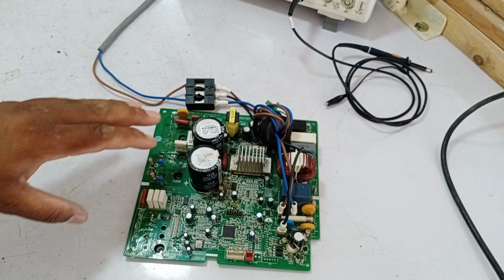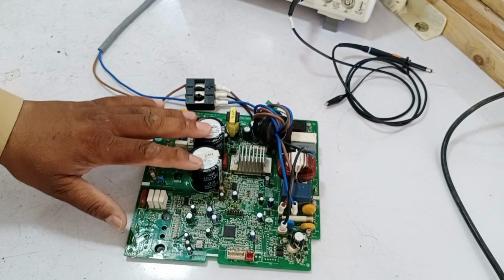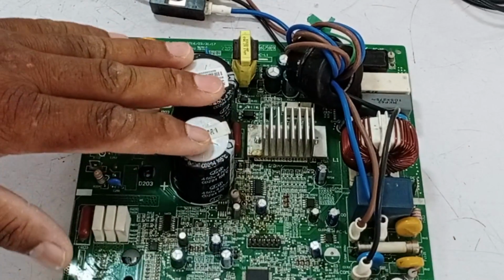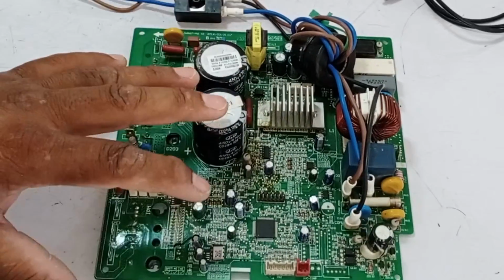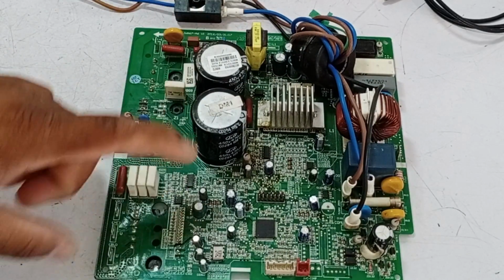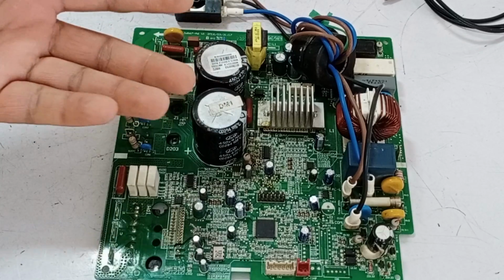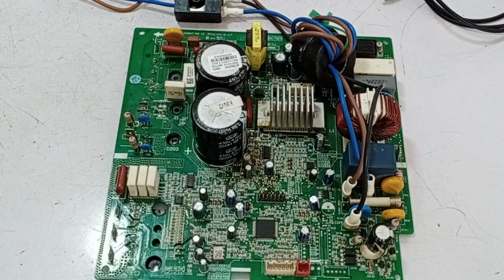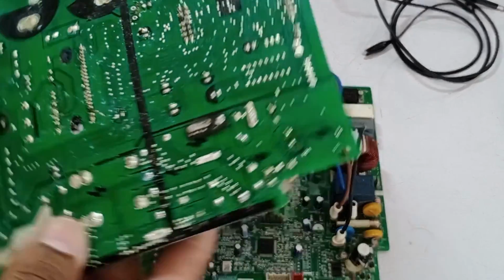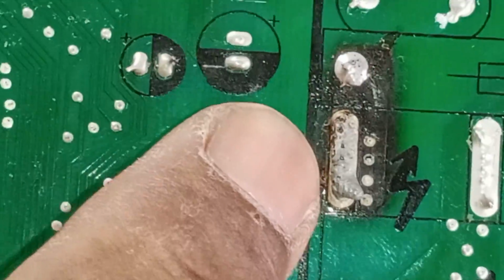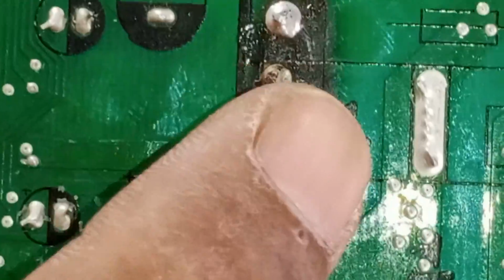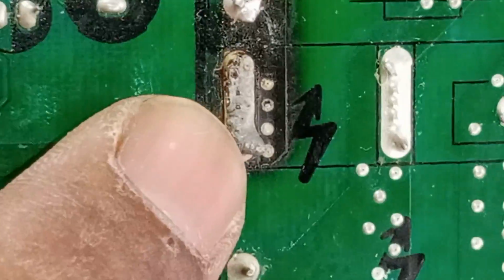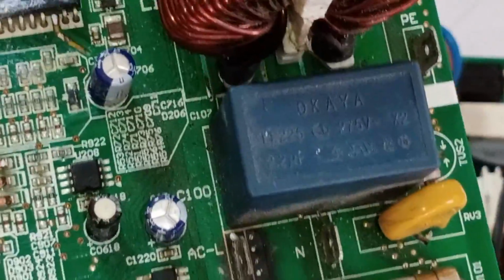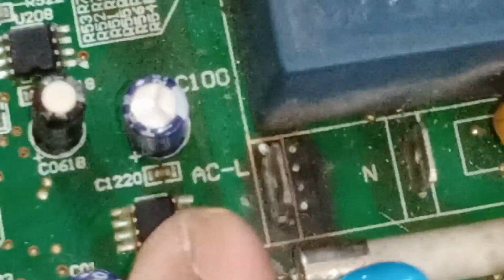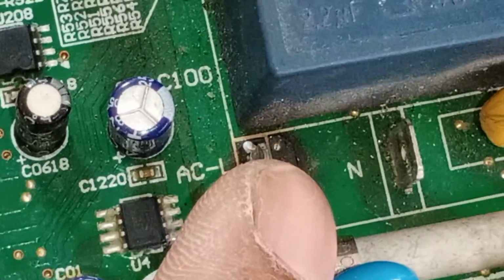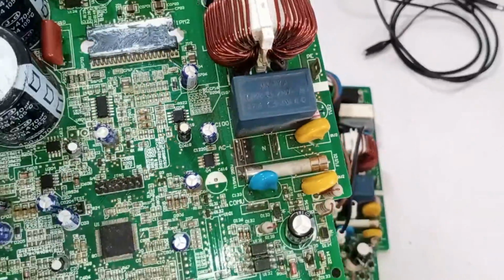Another possibility for the PL error code is that the voltage decreases in the circuit board due to these 2 power capacitors getting bad or weak. Then, voltages across the IPM will also be decreased, and the unit can show you the PL error code on the display. I have this other same circuit board. You can see that this trace over here has been burned, weakening the solder. This is making the voltages not pass correctly through the circuit board. This was burned from the main line, and this circuit board also showed the PL error code. I have fixed this circuit board, which had the PL error code.